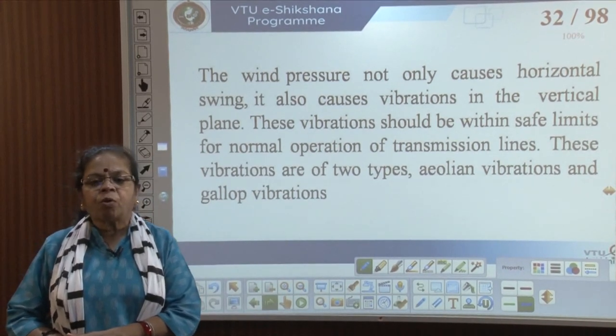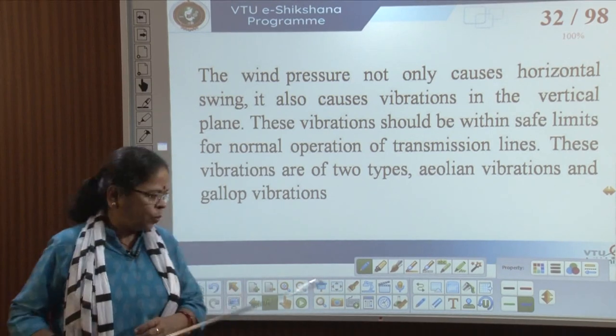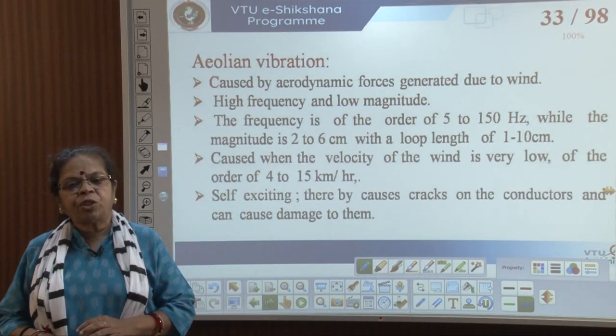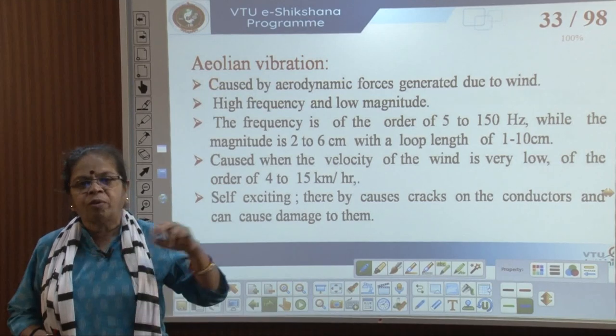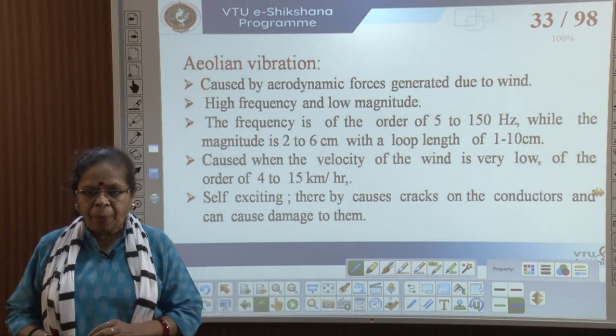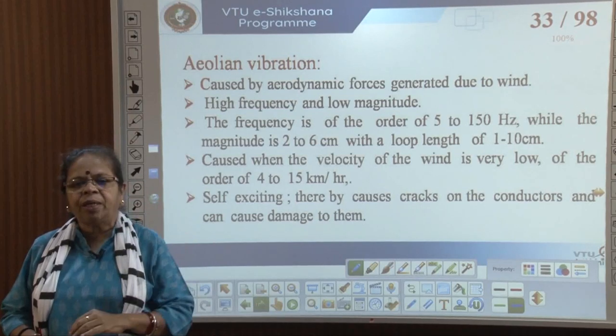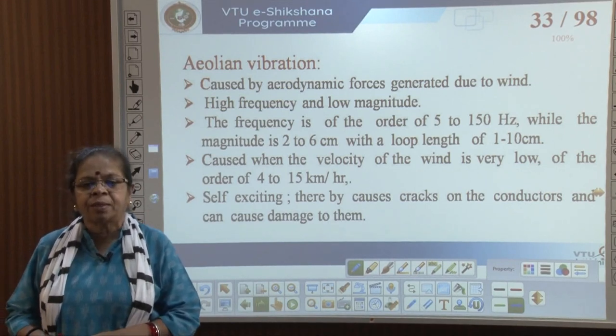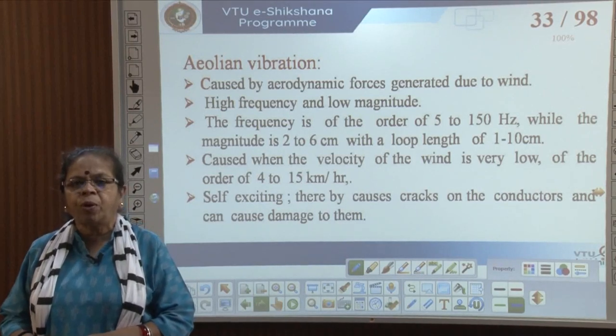These vibrations are of two types: aeolian vibrations and galloping vibrations. Aeolian vibrations are caused by aerodynamic forces generated due to wind, like on the wings of an airplane. They are of higher frequency compared to galloping but of low magnitude. The frequency is of the order of 5 to 150 Hz and the magnitude is around 2 to 6 centimeters, with a loop length of around 1 to 10 centimeters.